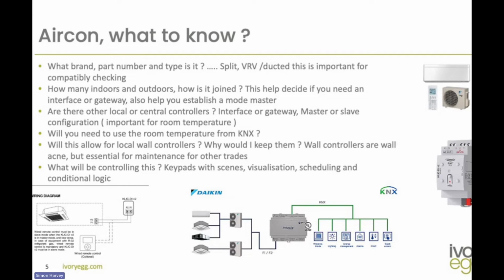For example, with an air conditioner, we tell it whether we want heating, cooling, or auto mode, and what set point we want that room to be. It will look into either a KNX provided temperature, a return air temperature, or a wall controller temperature input to work out whether it needs to increase or decrease to reach the set point.